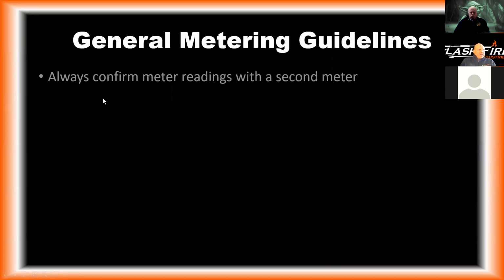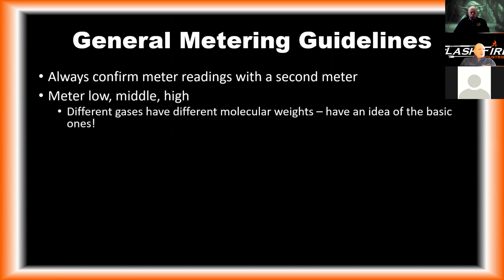So, some general metering guidelines. Always confirm meter readings with a second meter. Don't call in the cavalry from one meter reading. Things break, things can read differently, so it's always good to have a second meter to confirm the first readings. We want to meter low, middle, and high.